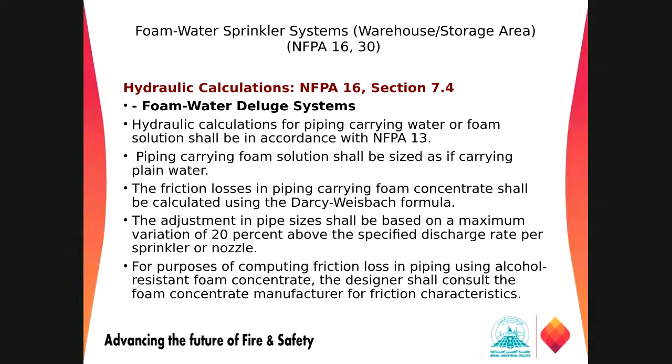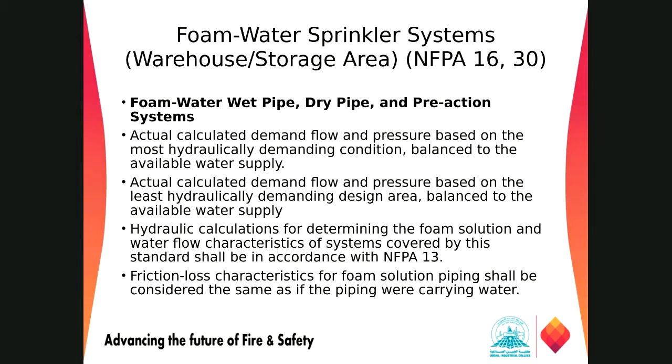And for the purpose of computing friction loss in piping using alcohol-resistant foam concentrate, the designer shall consult the foam concentrate manufacturer for friction characteristics, right? So we have to get the input from the data sheet for a more accurate calculation for our project.